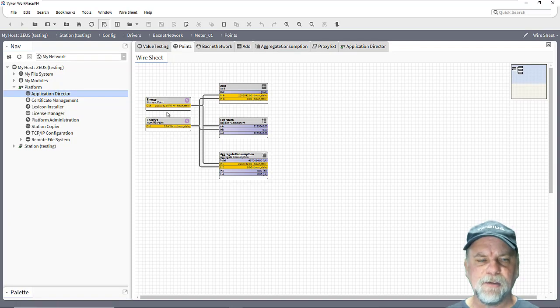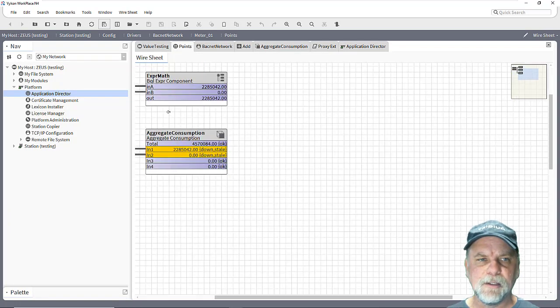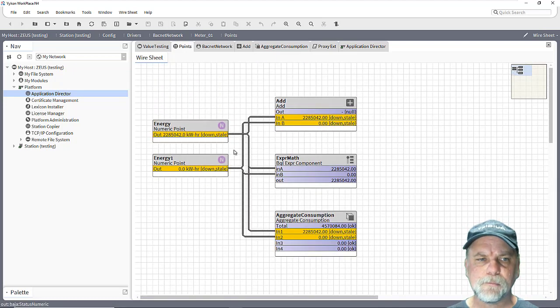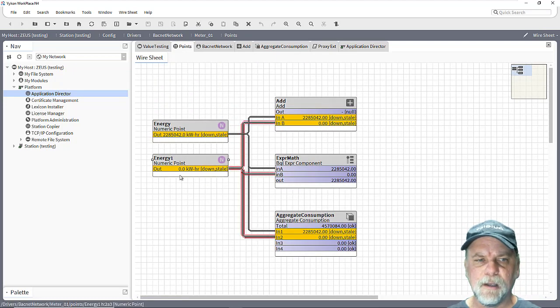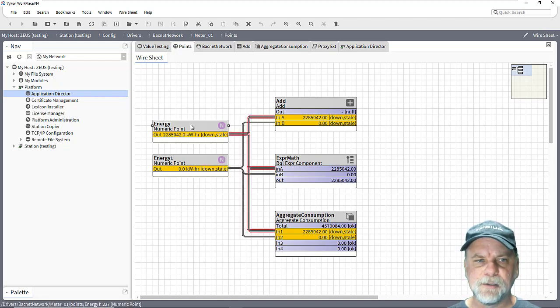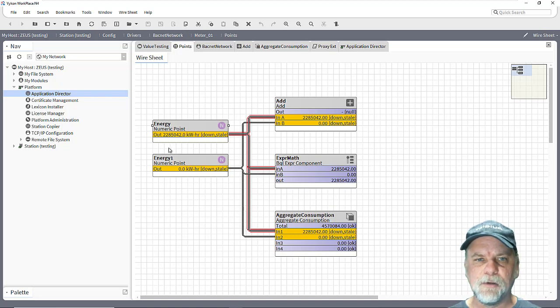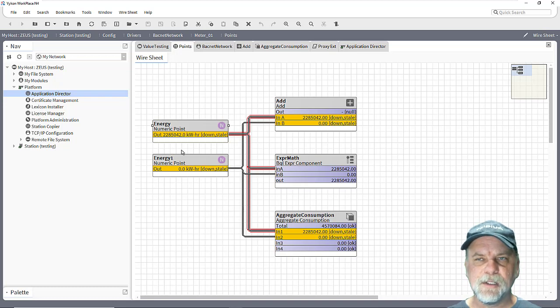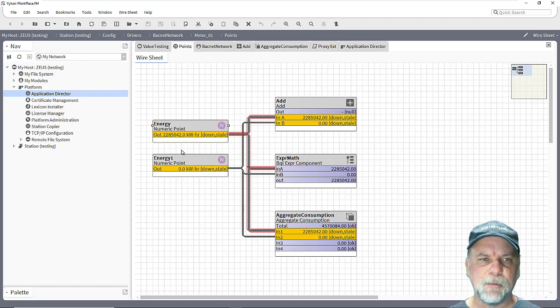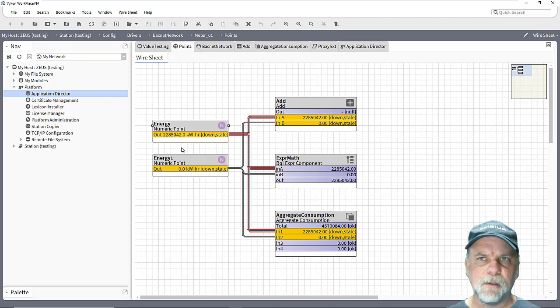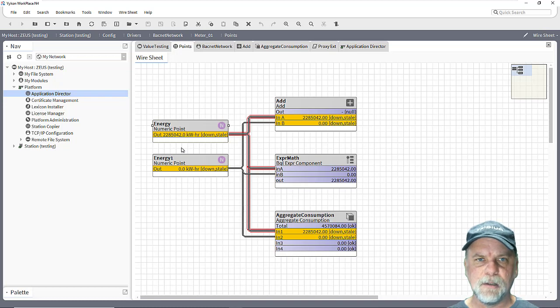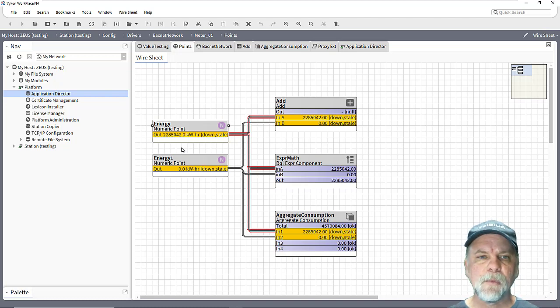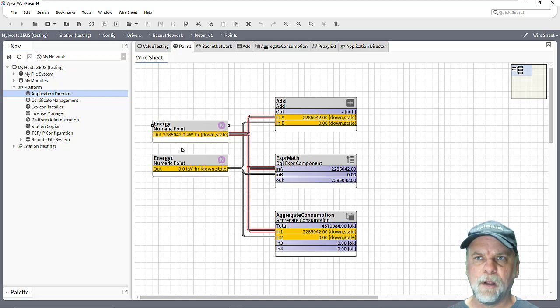And now if I take a look at this point wire sheet again, you'll see that this energy one point has a value of zero, whereas the energy two point has retained the last known value that we read from the device before the device went down. So this is an important type of concept when you're dealing with totalized values, particularly when the controller those values are persisted, so like a power cycle on that controller is not going to reset that accumulated total. And we know we want to hold on to that last known value.